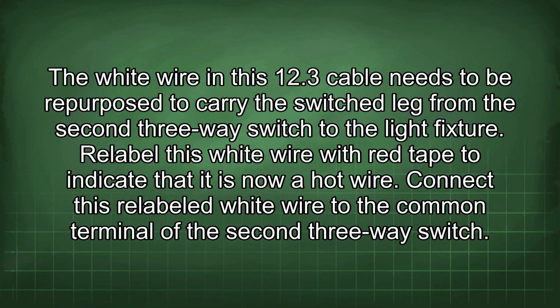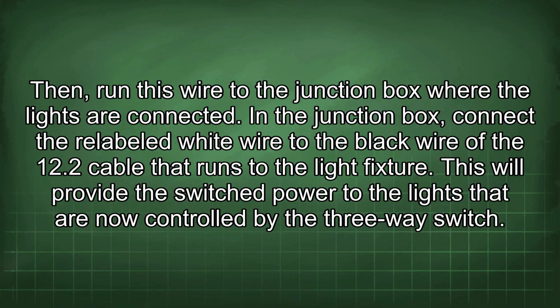The white wire in this 12.3 cable needs to be repurposed to carry the switched leg from the second three-way switch to the light fixture. Relabel this white wire with red tape to indicate that it is now a hot wire. Connect this relabeled white wire to the common terminal of the second three-way switch. Then run this wire to the junction box where the lights are connected. In the junction box, connect the relabeled white wire to the black wire of the 12.2 cable that runs to the light fixture. This will provide the switched power to the lights that are now controlled by the three-way switch.